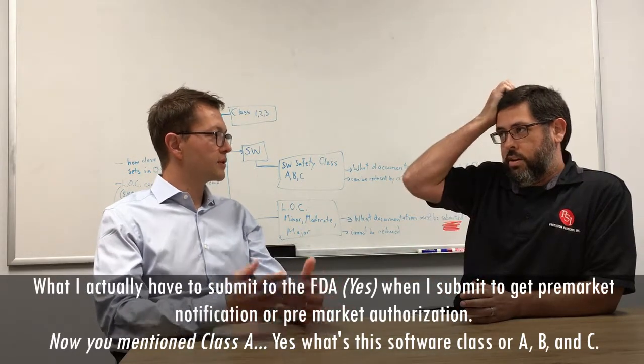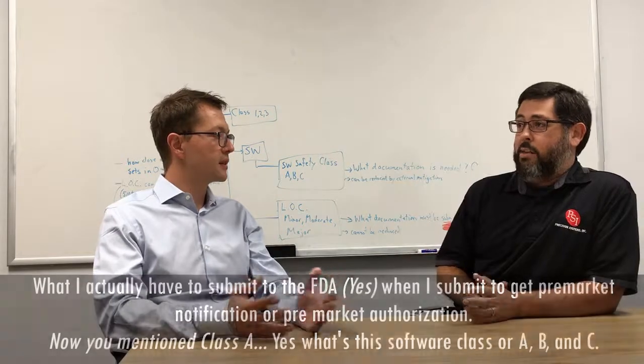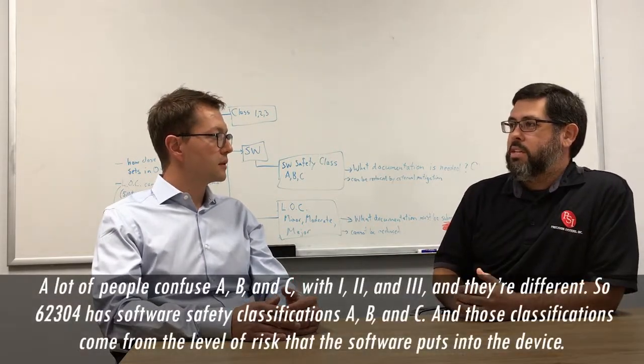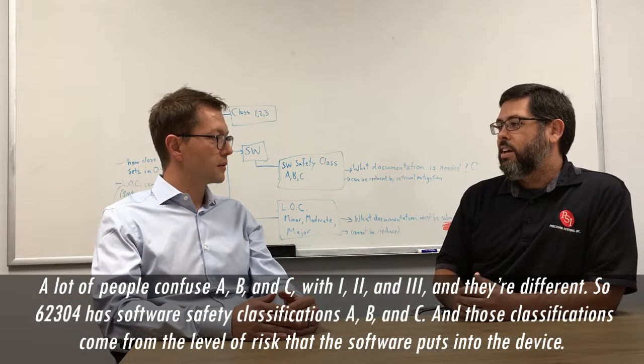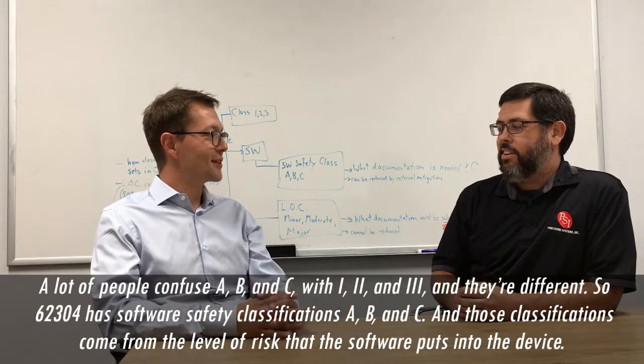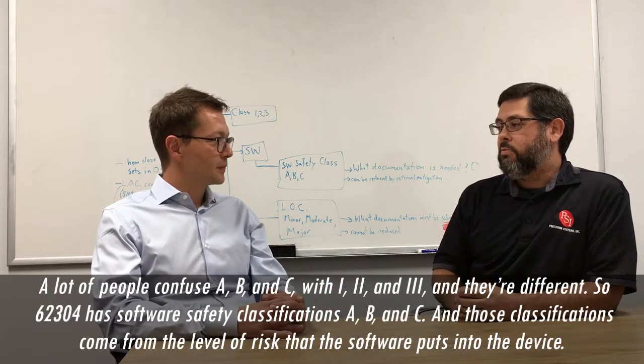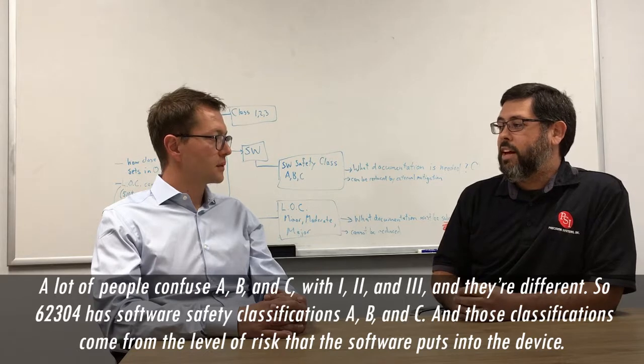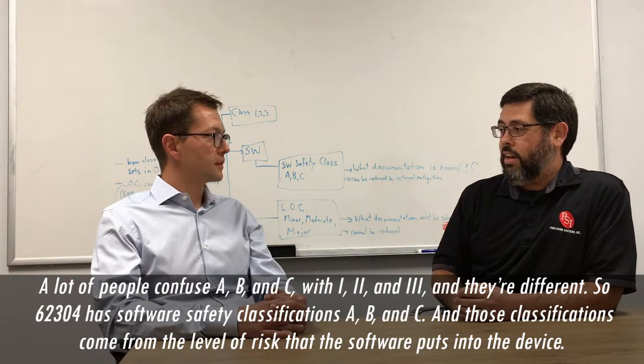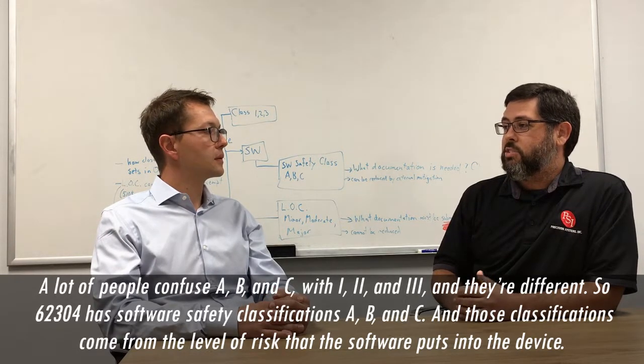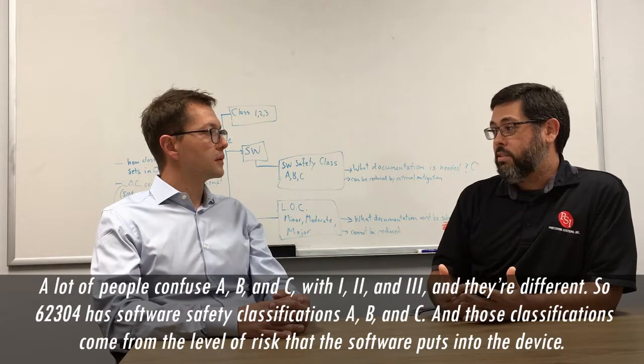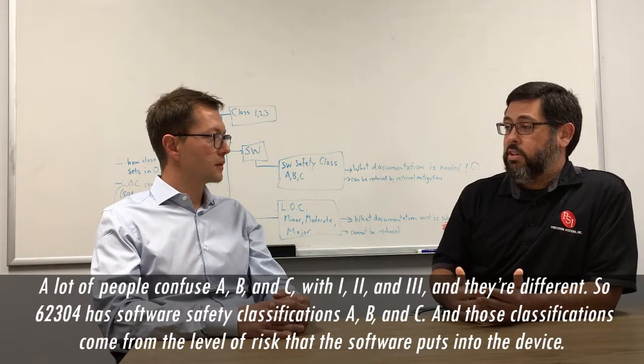What's software class? So A, B, and C? A lot of people confuse A, B, and C with 1, 2, and 3, and they're different. So 62304 has software safety classifications A, B, and C. And those classifications come from the level of risk that the software puts into the device.